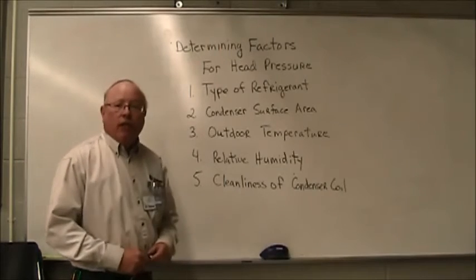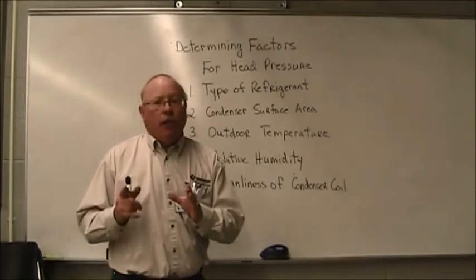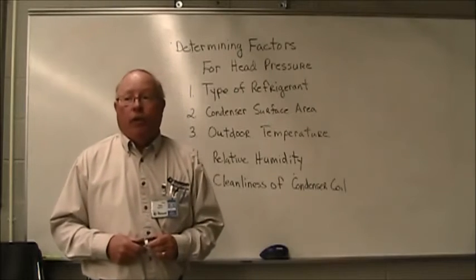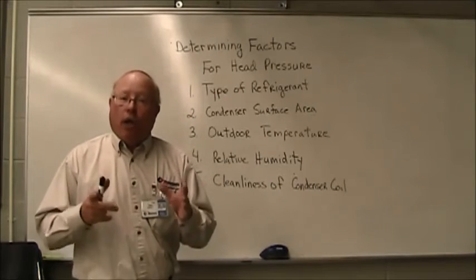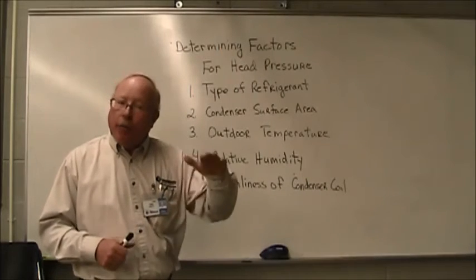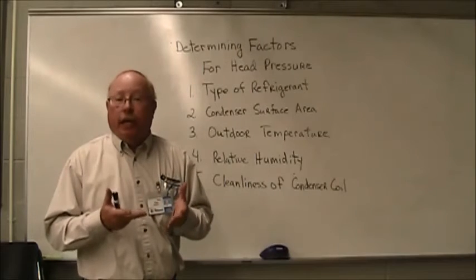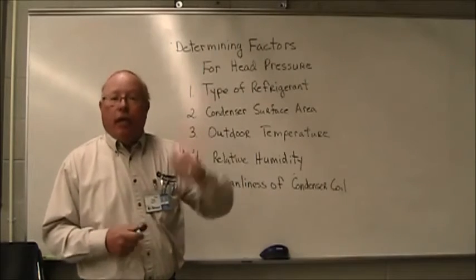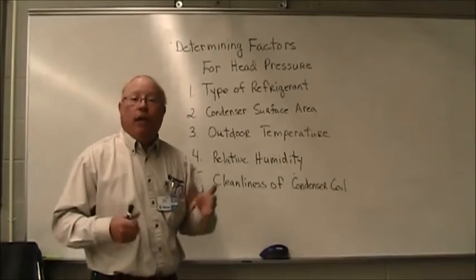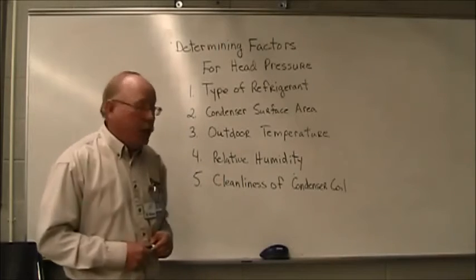What is the relative humidity? The humidity is going to decide how much heat can be held within the air. So on low humidity days, our head pressure is going to be lower. On high humidity days, with a higher relative humidity, the pressure is going to be much higher.